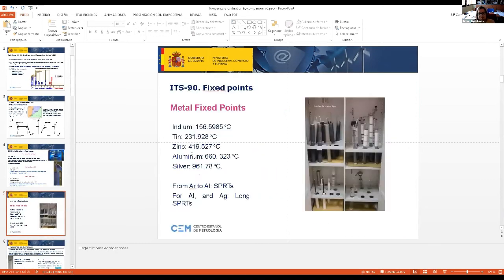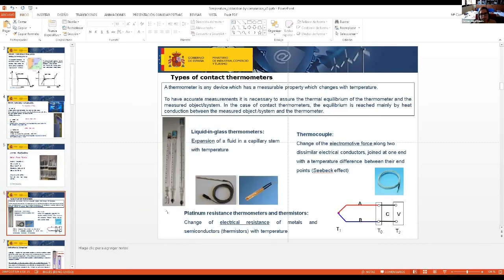Of course, this scale covers a higher temperature range up to almost 1000 Celsius degrees, and also in the negative part down to the argon point. These fixed points are usually used for the calibration of standard platinum resistance thermometers. But we have other types of thermometers. You know that a thermometer is just a device where one of its properties changes with temperature. That's all.